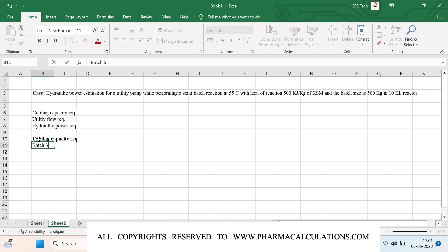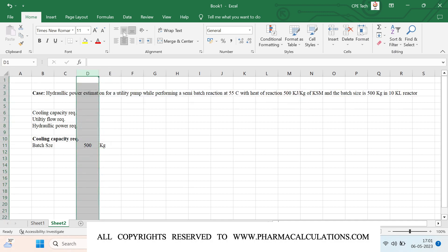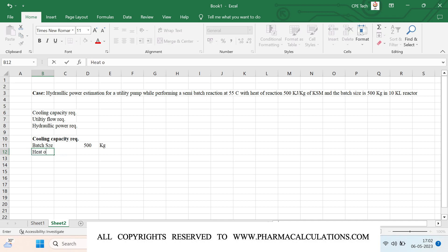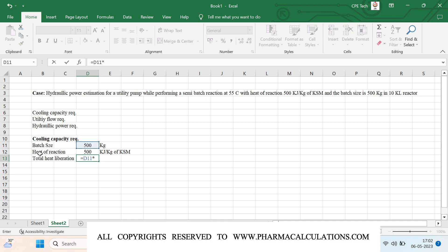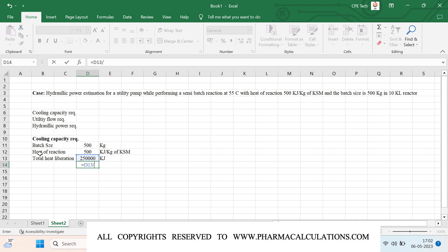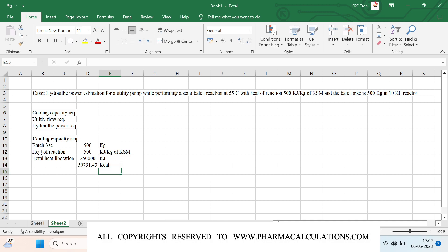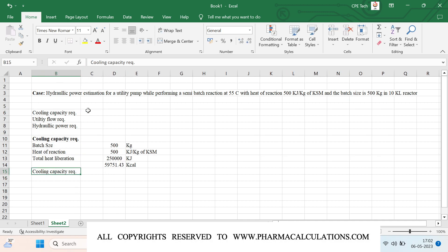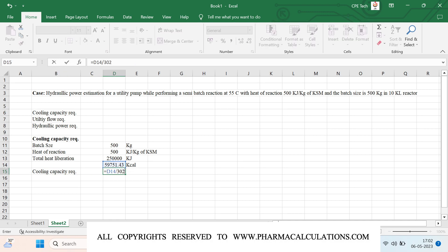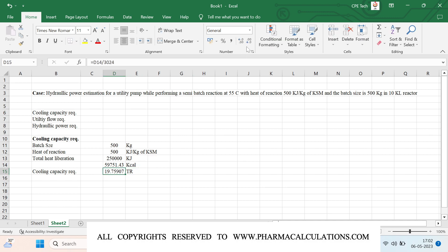For the cooling capacity requirement, the inputs are the batch size of 500 kg and the heat of reaction of 500 kilojoules per kg of KSM. The total heat liberation is 500 multiplied by 500, giving 250,000 kilojoules. Converting to kilocalories by dividing by 4.184 gives approximately 59,751 kilocalories. The cooling capacity requirement is then total heat liberation divided by 3024, giving approximately 20 TR.